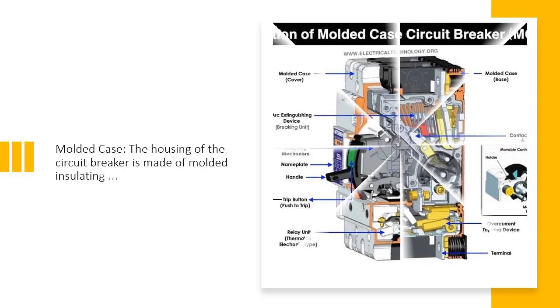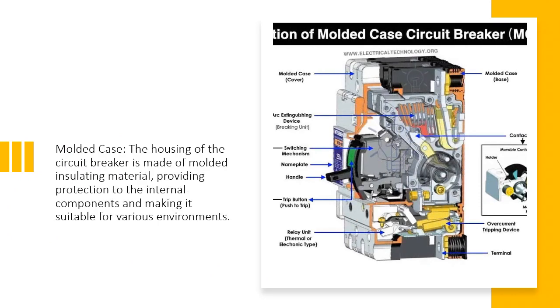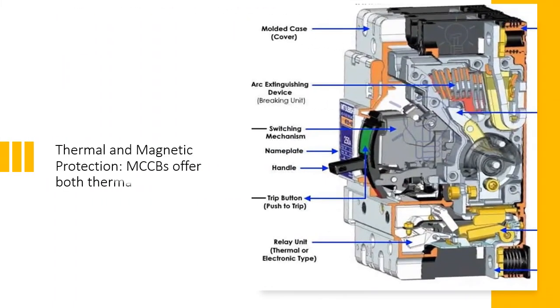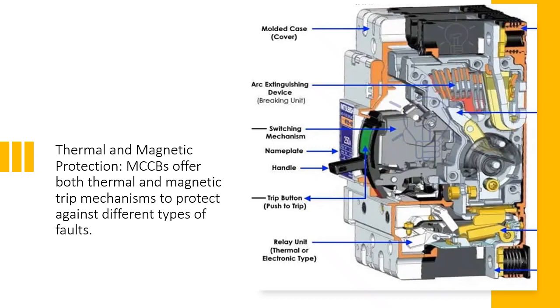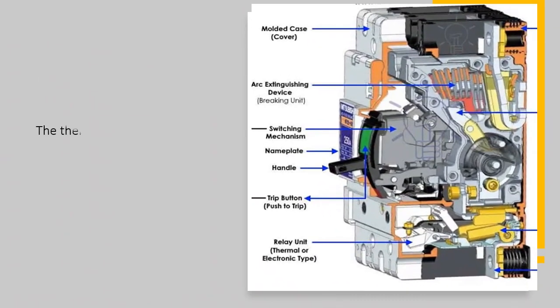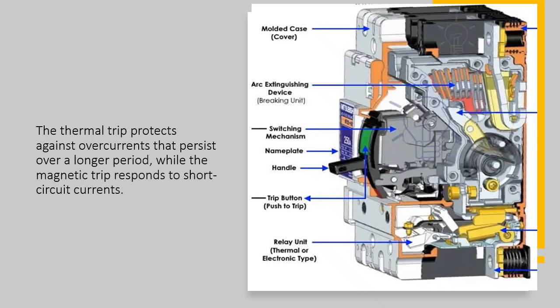Key features of MCCBs include: 1. Molded Case — the housing of the circuit breaker is made of molded insulating material, providing protection to the internal components and making it suitable for various environments. 2. Thermal and Magnetic Protection — MCCBs offer both thermal and magnetic trip mechanisms. The thermal trip protects against overcurrents that persist over a longer period, while the magnetic trip responds to short circuit currents.